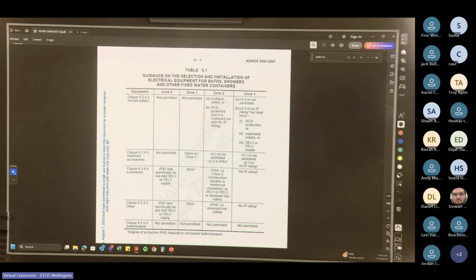Cool. So luminaires no longer need IP rating in zone 3. Anything else does not need IP rating in zone 3, but again, switchboards are not allowed. And a degree of protection of IPX5 is required in communal baths or showers in zone 1 and 2, or any zone 1, 2, and 3. So IPX5 is required for communal baths and showers.